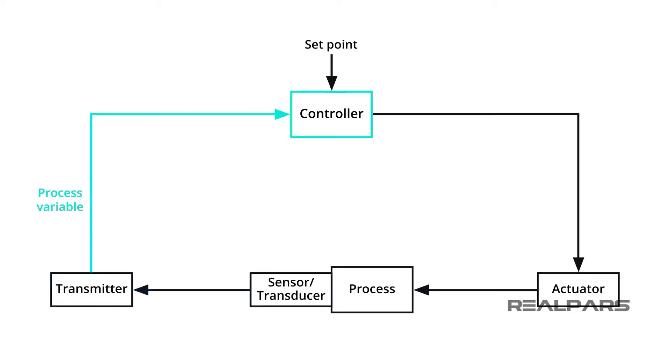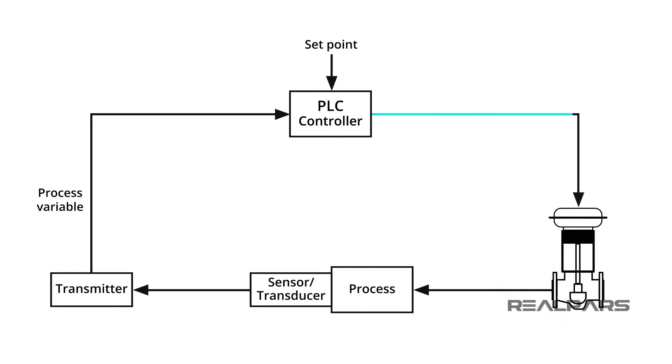The controller is the device that looks at the difference between the process variable or PV and the setpoint or SP. The controller then determines what action to take place and generates an output signal that is a function of the result of this comparison. Controllers are either a DCS or a PLC in process control today. The final actuator is the device such as a valve that exerts a direct influence on the process as directed by the controller.